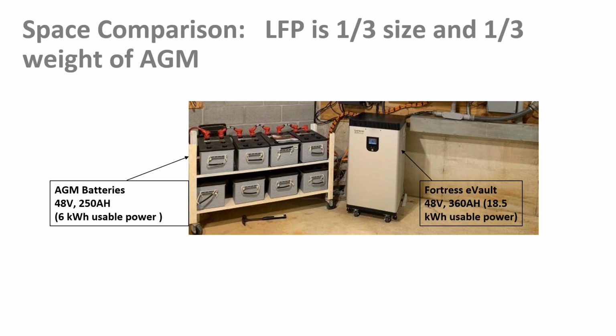Next slide, please. If we look at the space comparison of LFP versus an AGM battery, you can see on this picture we have the Fortress eVault 18.5, a beautiful unit, and then here some AGM batteries. Even so, this is 250 amp hours of battery bank versus 360 amp hours. So this eVault is less than double the size of this bank here on the left, but has 110 more amp hours of capacity. Wow. So really, LFP in comparison to lead acid is not only a third the size and a third of the weight, but you can use it more. There's no maintenance. There's a lot of benefits to switching over to lithium, especially from the traditional lead acid approach.